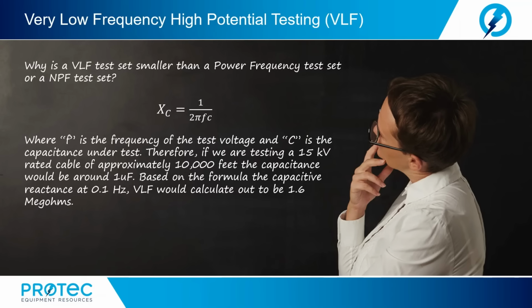Again, let's go back to our example of a 15 kV cable of approximately 10,000 feet in length. The capacitance, once again, would be about 1 microfarad. Now, instead of using 60 Hertz, let's substitute the frequency of 0.1 Hertz, and let's see what our calculation brings us. Well, it will bring us to 1.6 megohms, as we see here.